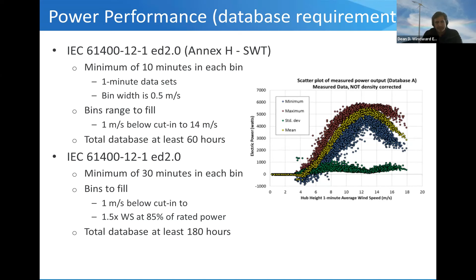So how long does it take? That depends a lot, but it used to be sensitive to the sectors that were valid — you had to have all your winds coming from those valid sectors. ACP opens that up and says excluded sectors are now allowed, as long as the anemometer is not affected. So obviously you can't have a sector where the anemometer is behind something, particularly behind the wind turbine.